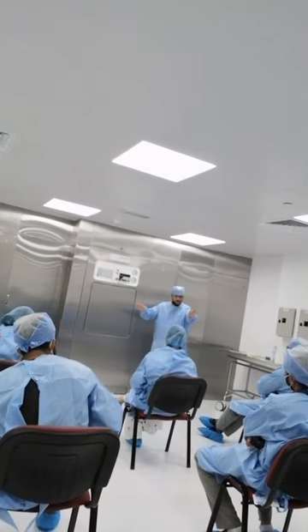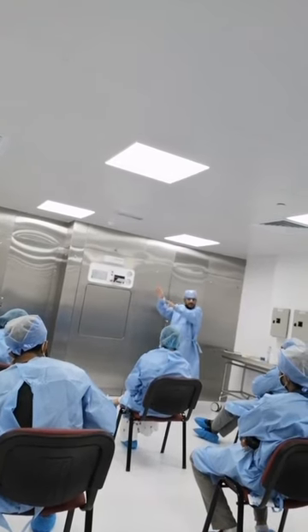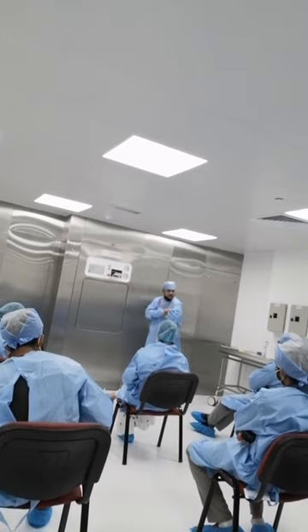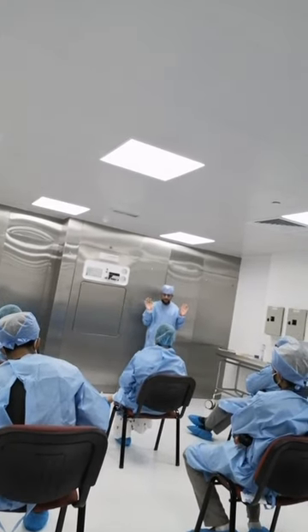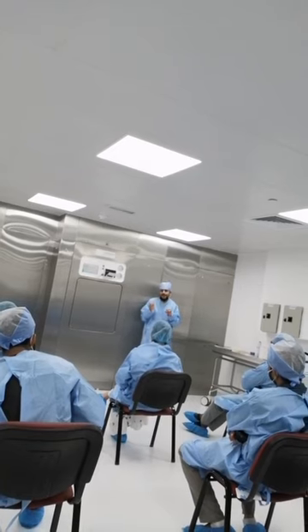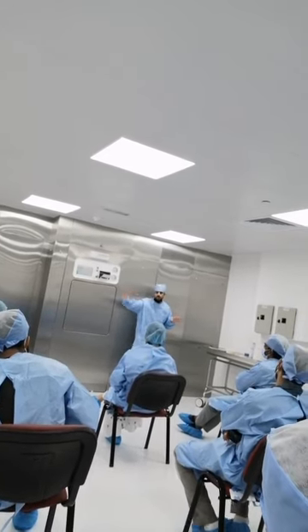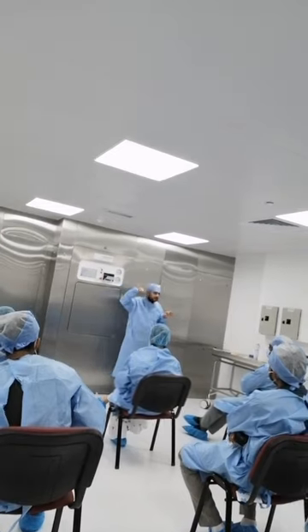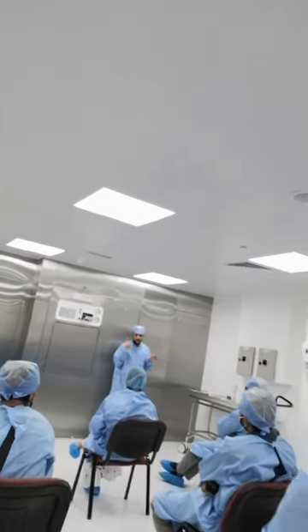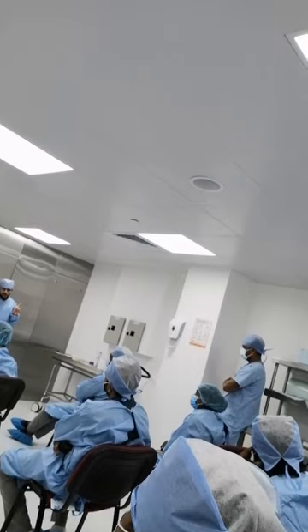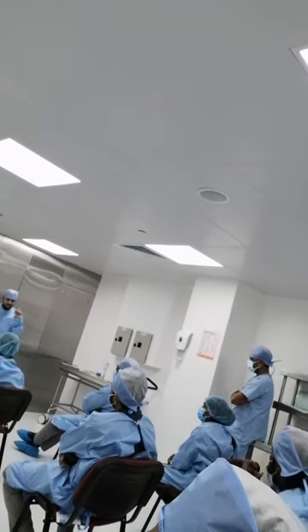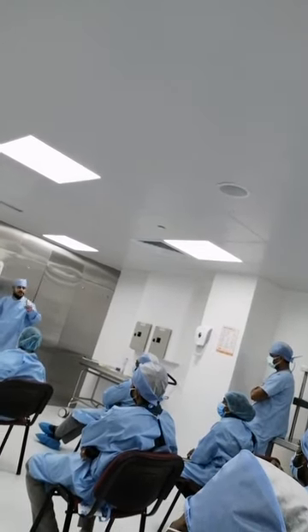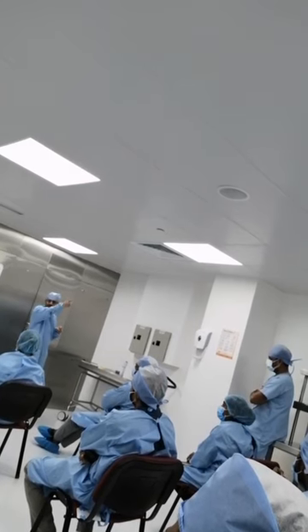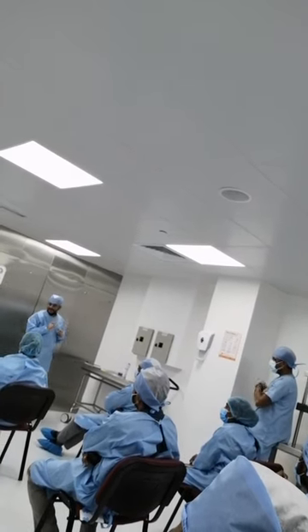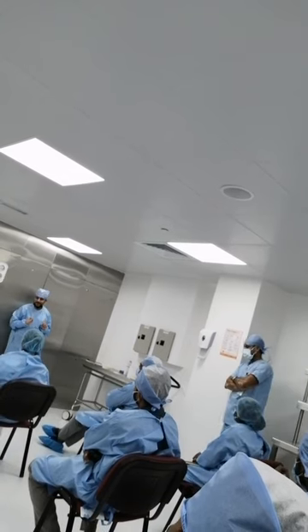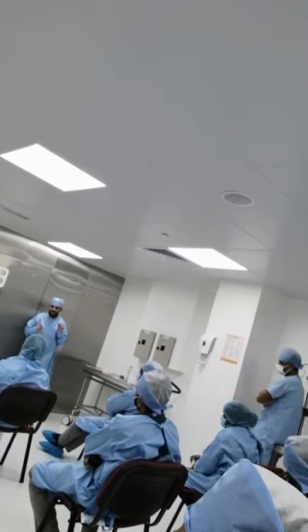All machines are sterilizing. All of them are sterilizing. Why do we have certificates saying this? There is no worry at all that if you get any of these manufacturers, it will not sterilize. But put into consideration time. Okay? So when I came here, the boss said that this is a thermal machine, it has a booster. See how he's happy? Because it finishes the cycle fast. Because if you don't have the booster tank, it will take 1 hour, 5 minutes. He's happy because it's fast.